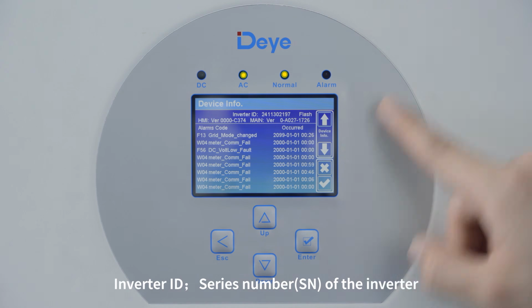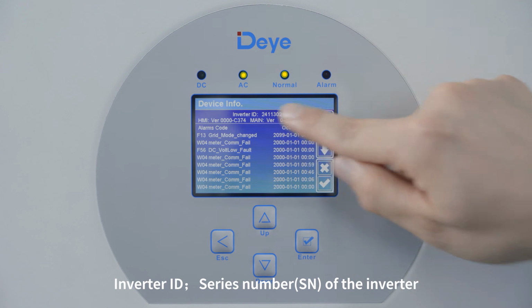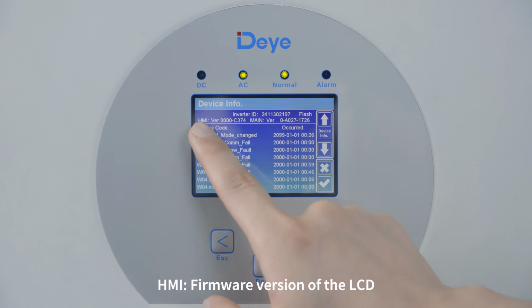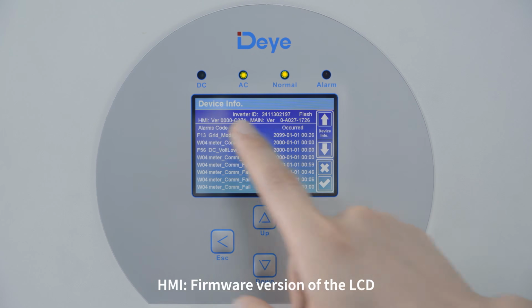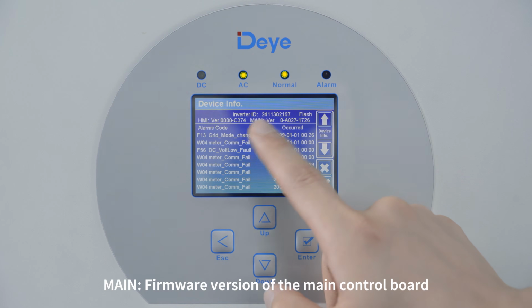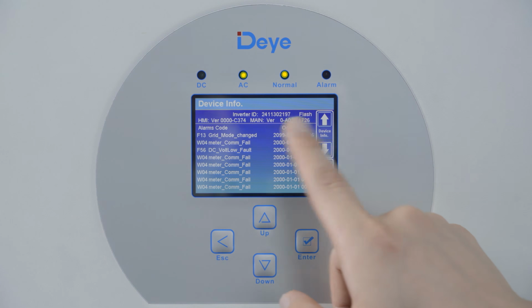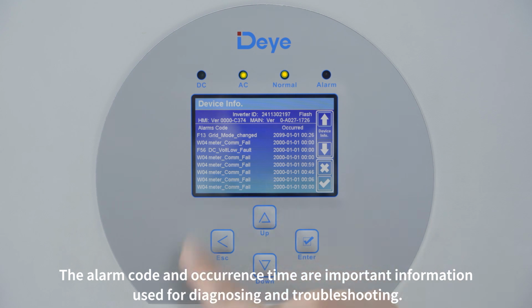Inverter ID: the serial number, SN, of the inverter. HMI: the firmware version of the LCD. Main: the firmware version of the main control board. The alarm code and occurrence time are important information used for diagnosing and troubleshooting.